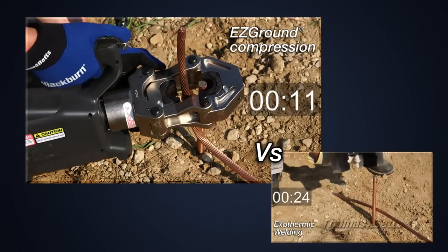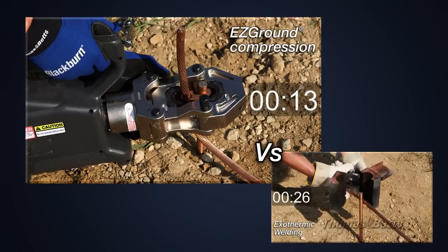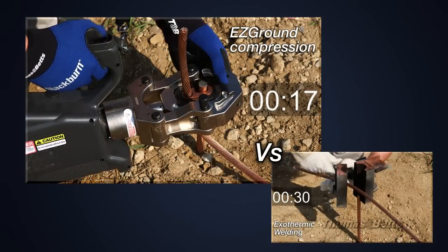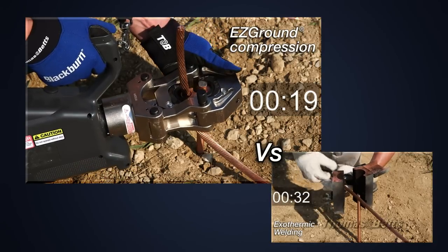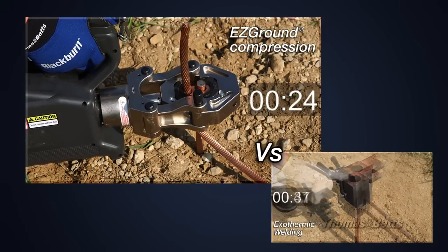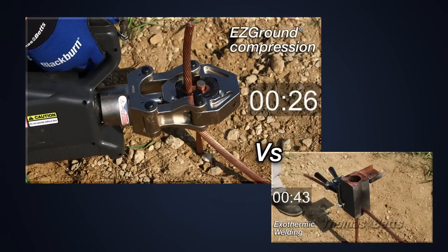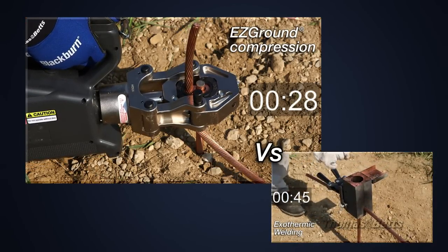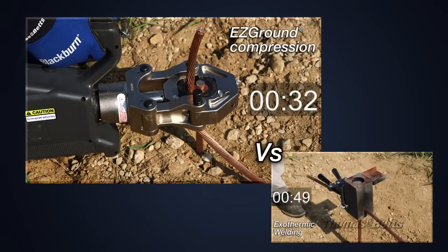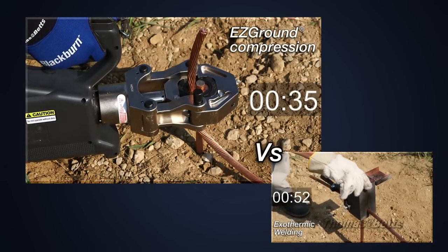Exothermic welding requires special precautions or equipment in wind to retain the welding powder in the crucible, in rain to keep the welding powder dry, and in cold to meet minimum installation temperatures. EZGround does not require special precautions or equipment. It was designed to simplify and speed up the entire procedure. Compression terminations can be done in even the most difficult weather conditions.